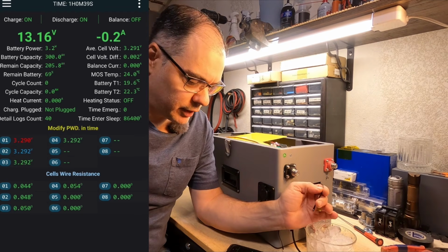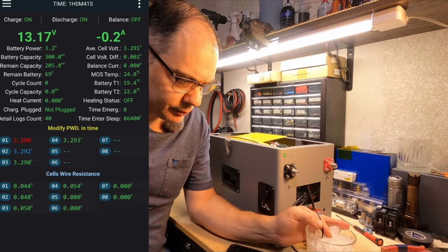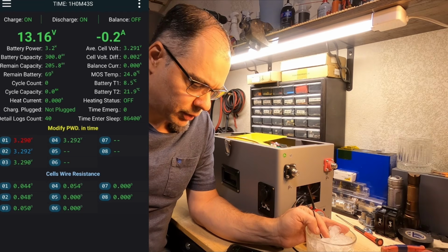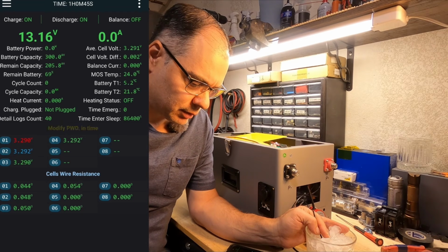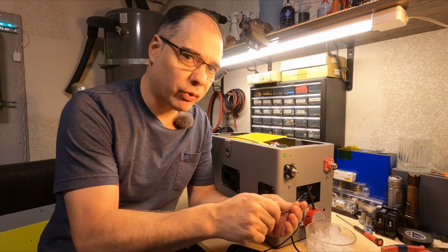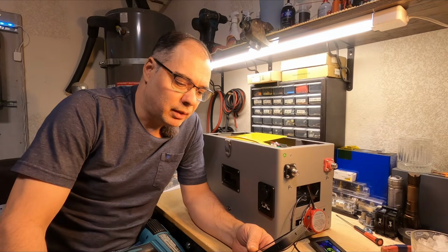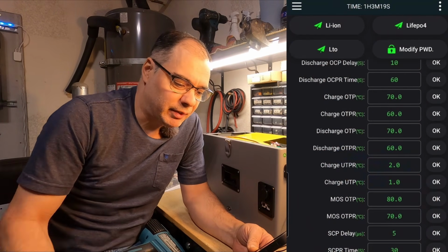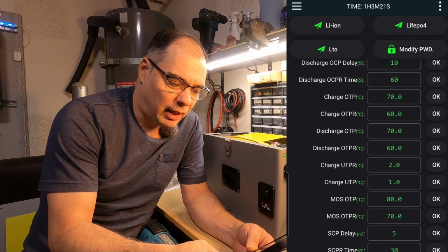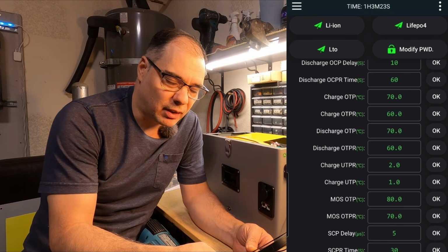There it goes, alarm is cleared. Works good. Let's see if T1 responds in the same way. We're just looking for it to drop - yep, it's dropping fast. So these temp sensors are probably both low and high temp. Our high temp value is set at 70 degrees Celsius and our return is 60 degrees Celsius.